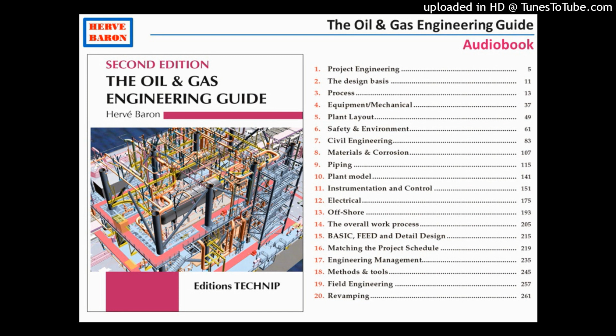The fire-water network entails a looped fire-water distribution ring, together with numerous isolation valves and hydrants which have to be accessible from the road. As you see, we have seen that there is a number of systems: the rainwater collection systems, the process drain systems, the underground cable systems, the fire-water systems. All these systems have to be coordinated by the civil engineer.